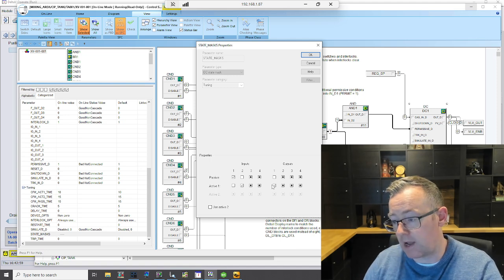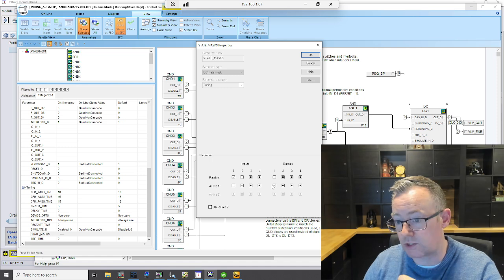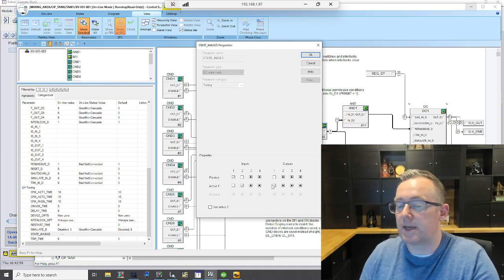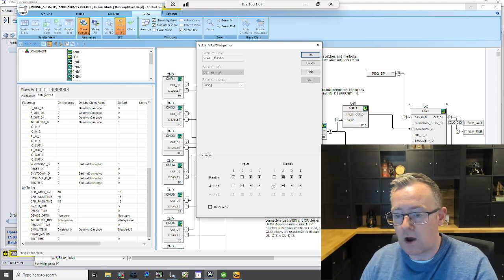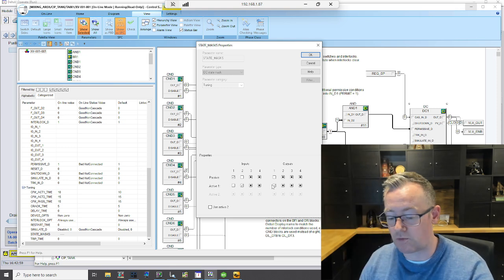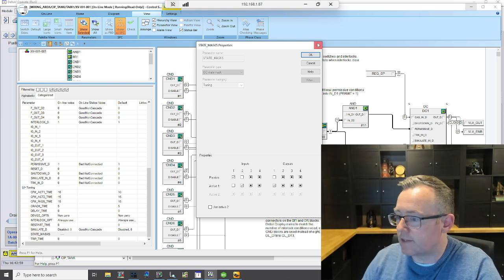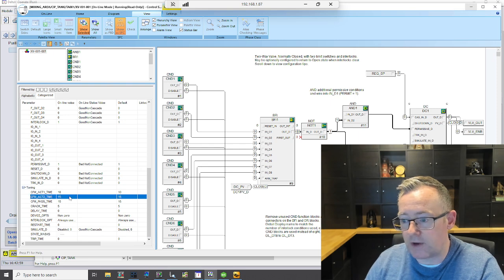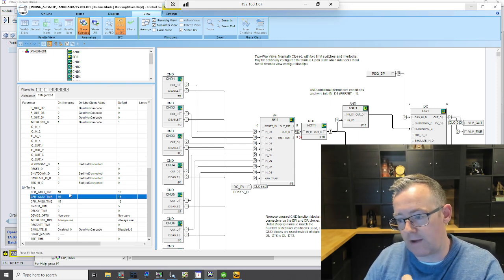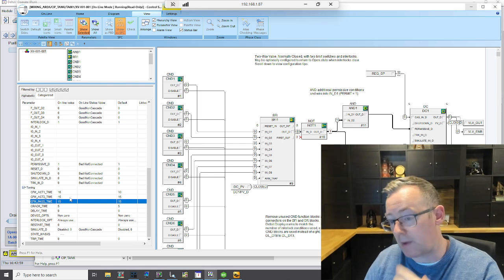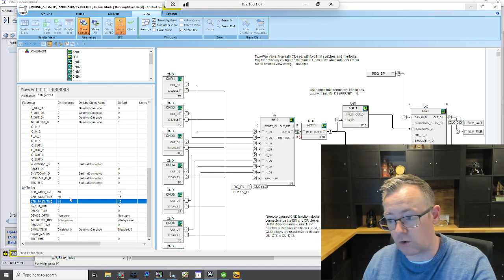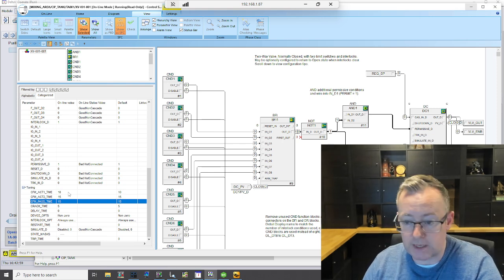So, for example, some kind of a relay, which basically allows pressurized air to go to a valve so it opens, for example, right? Or in a case like this, it's a motorized valve, right? And then we have items here, like the actual time it takes to get to active, or the time it takes to get to passive, to open a valve or to close a valve, and what's actually allowed in that sense, right?